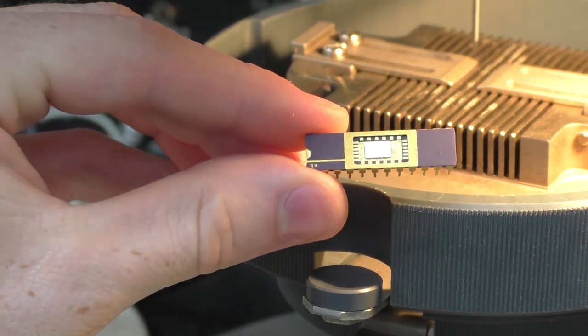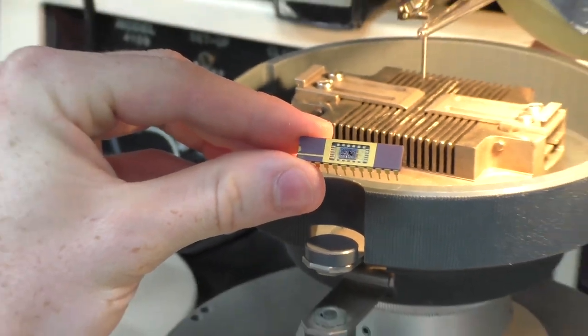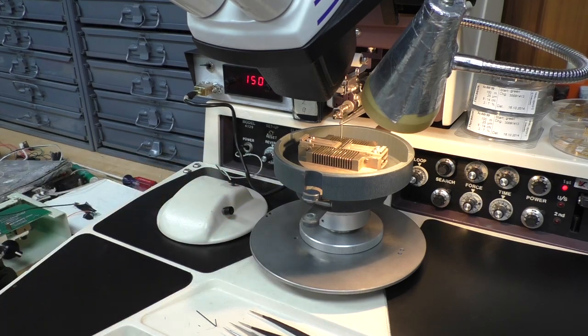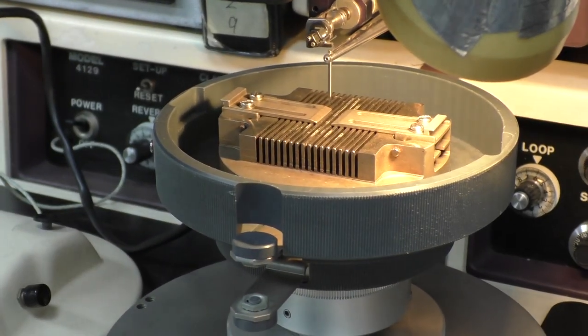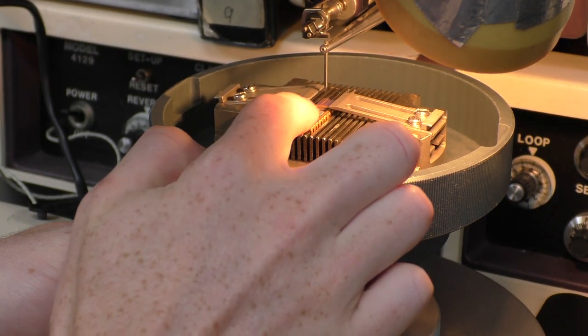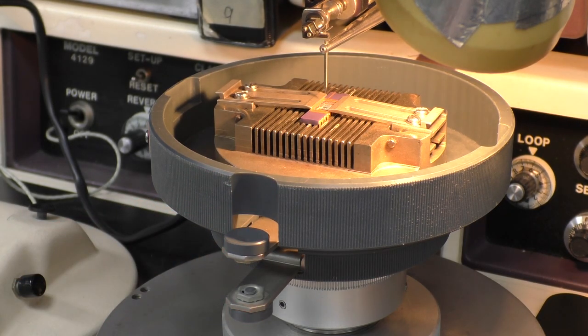The chip I'll be doing for a demo I've used to calibrate all the settings and probably done a few hundred test bonds on, so it's really scratched up and it's a total mess. After you make bonds to a metal surface it gets pitted and kind of scratched up. You can rip off the bond wire and try again but there's only so many times you can do it and you'll see just how bad those metal surfaces look under the microscope.